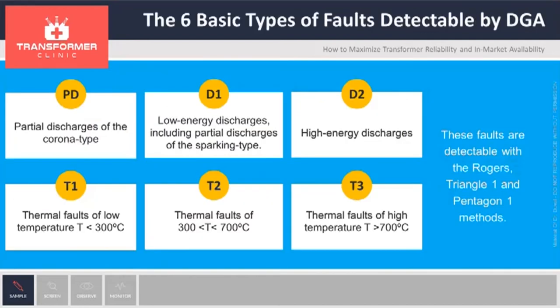Six basic types of faults are detectable by DGA: corona partial discharges PD, low energy discharges D1, high energy discharges D2, and thermal faults T1, T2, T3 of different temperatures. They are detectable, for instance, with Triangle 1 and Pentagon 1.